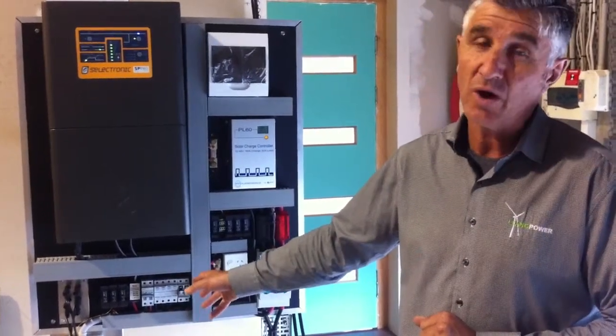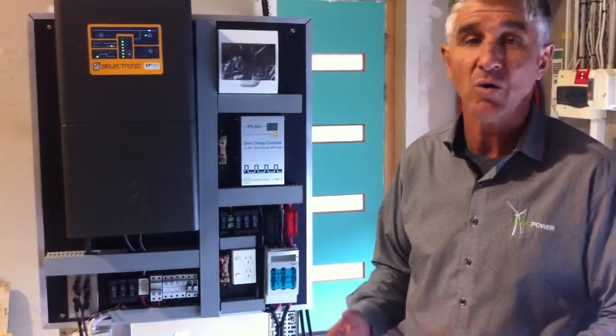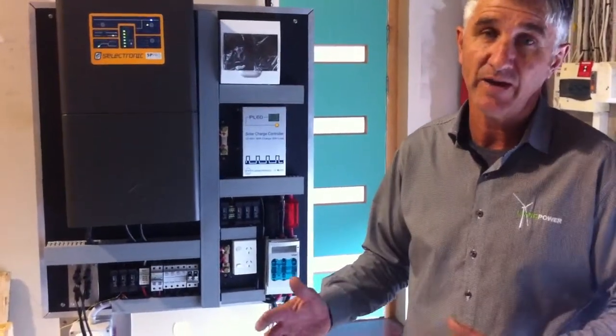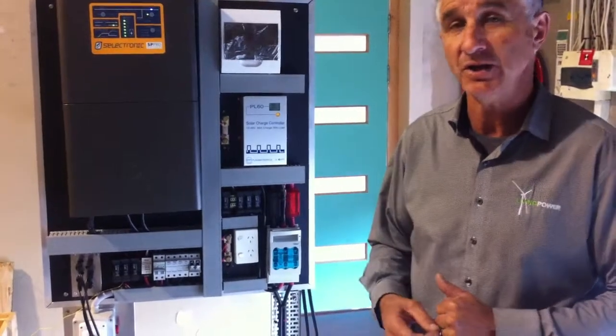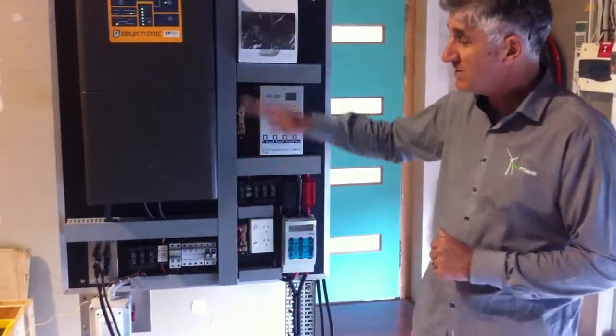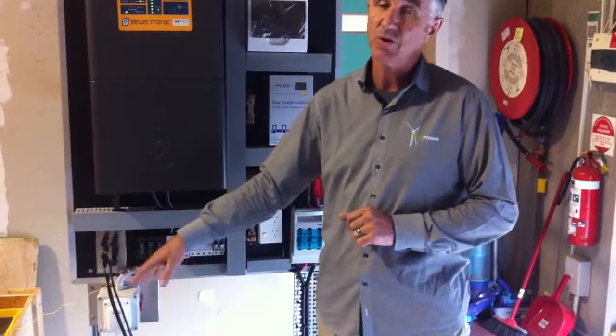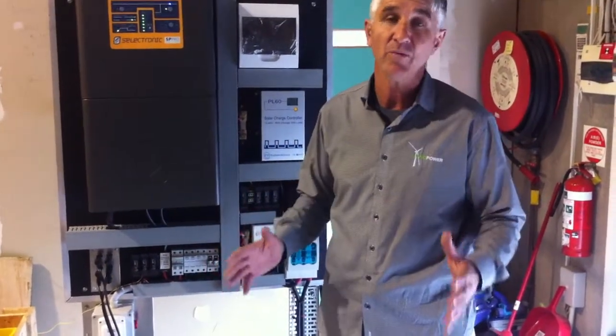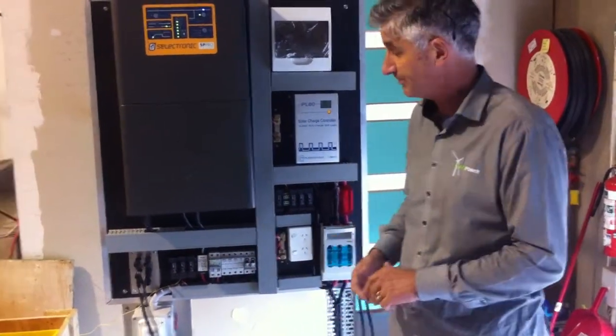Often that light will come on if you've had a few days of fog or you've been using the system fairly heavily and drawing a lot of energy out of it. Generally the systems are designed so that you're only operating in the top 20% of the batteries, and that way you'll get maximum battery life.